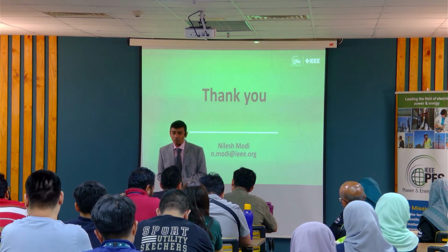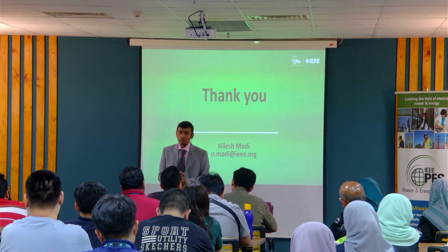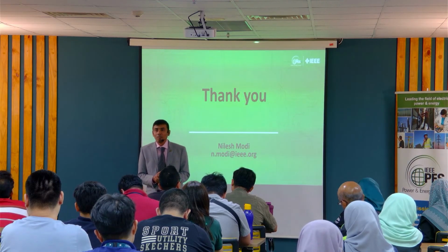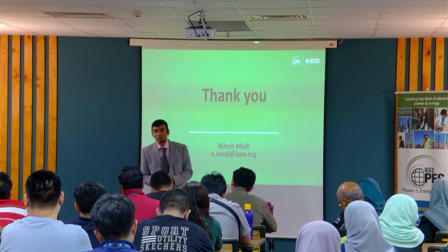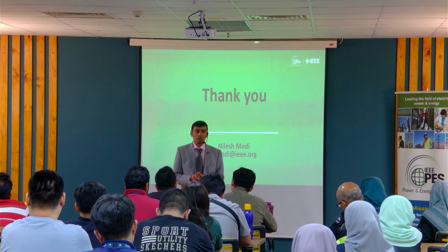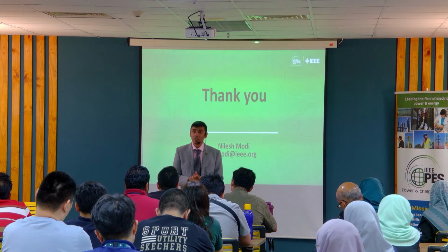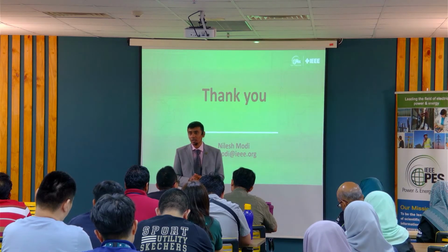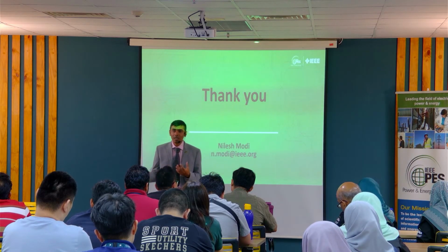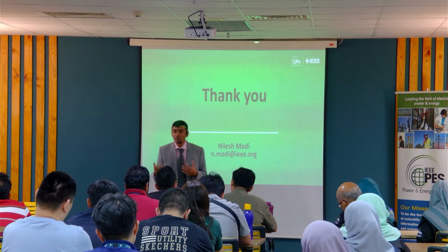So I'm guessing you would have enough supply demand balance to meet it. But if you do not have sufficient, let's call it system strength to manage those PV online, then you have to curtail back. Because curtailing happens for a lot of reasons.